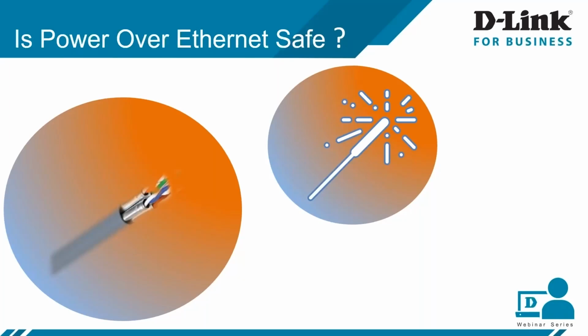Now let us discuss the worst case scenario when we are talking about fire safety when it comes to PoE. If we are not following any standard, any guidelines, or any certification, then what will happen? The installer or anyone can do as per his own wish. There could be a large tight bundle simultaneously delivering high power, 60 watt, placed in a hot ceiling space above 40 degrees centigrade from one point to another without breaking the bundles into smaller ones. It also has, let us say, low quality unshielded cable. Instead of copper, we are using copper clad aluminum in close proximity to combustible material.